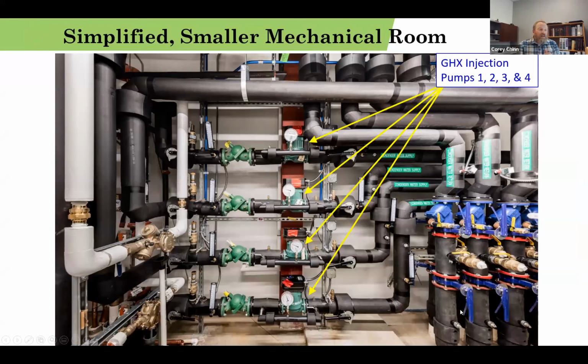All right, our ground loop, super exciting. This was the first time we tried it. We had 32 holes. We did 8 holes on each header pair, and then we put an injection pump on each header pair. So these are our injection pumps. And then sitting down over here on the right-hand side, you can see our base-mounted building distribution pumps. So these pumps circulate water through the ground loop, and we're decoupled, and we circulate this water over here through the building.